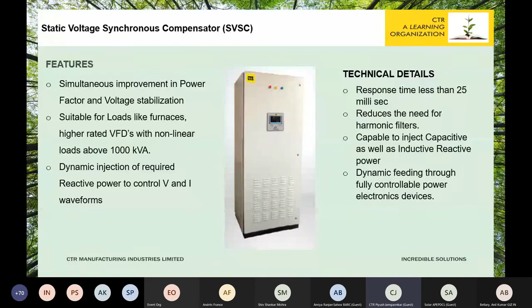The VSCs are the heart of any STATCOM, which uses DC capacitors to provide input voltage and a small amount of active power. Also, they absorb the reactive power, which helps to stabilize the voltage, and operate with ultra fast response time to compensate for voltage dips and flickers and control the PF also, thereby reducing the need for separate harmonic filters. The STATCOM is able to inject capacitive as well as inductive reactive power, and this is dynamically fed through fully controllable power electronic devices.